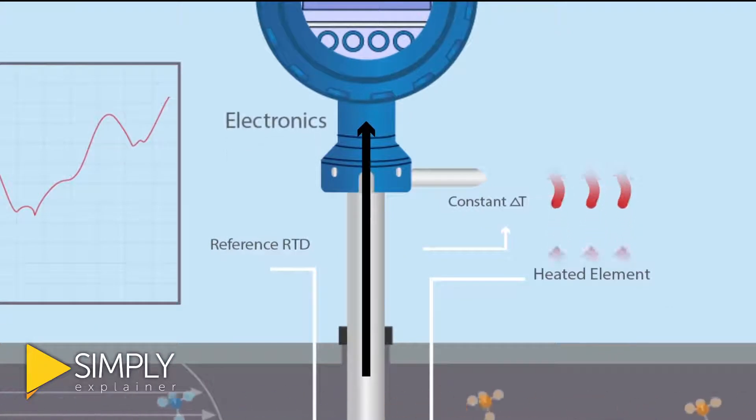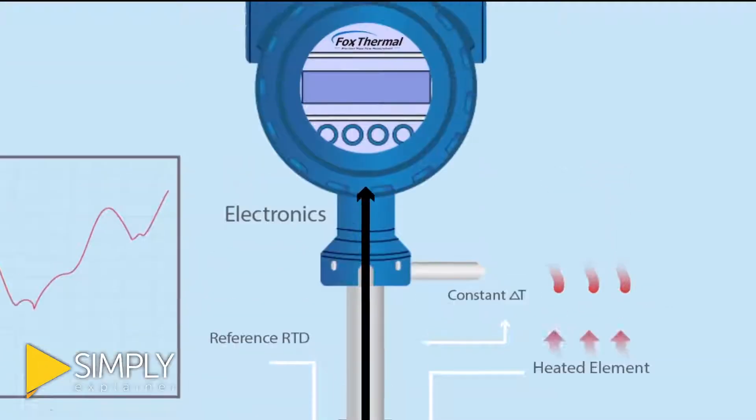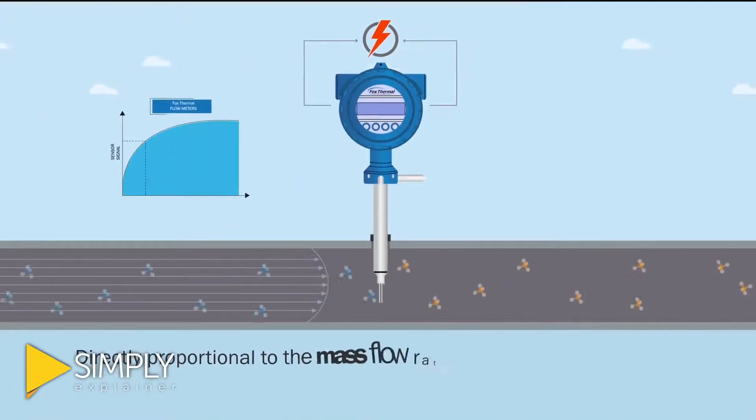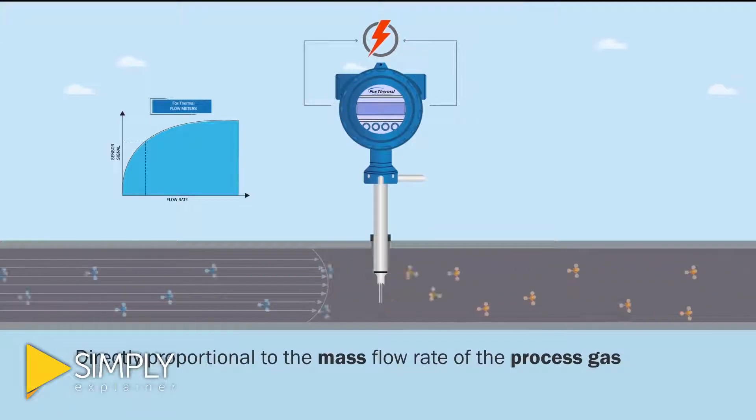The flow meter electronics measure the cooling effect of the gas flow and the electric power required to maintain a constant temperature differential, which is directly proportional to the mass flow rate of the process gas.